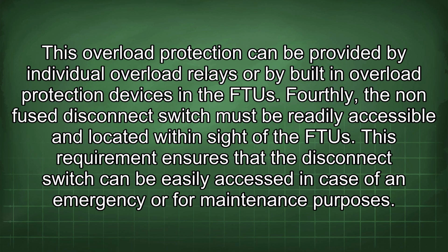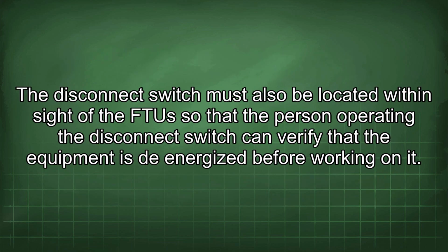Fourthly, the non-fused disconnect switch must be readily accessible and located within sight of the FTU. This requirement ensures that the disconnect switch can be easily accessed in case of an emergency or for maintenance purposes. The disconnect switch must also be located within sight of the FTU so that the person operating the disconnect switch can verify that the equipment is de-energized before working on it.